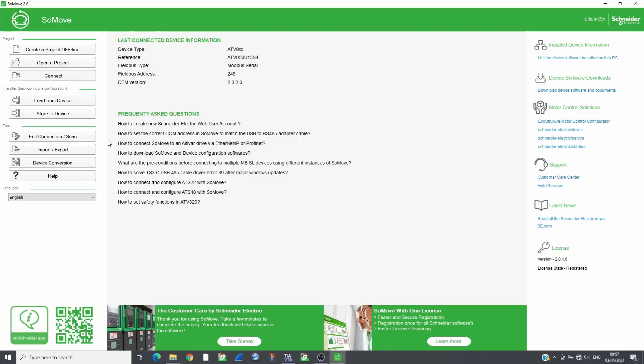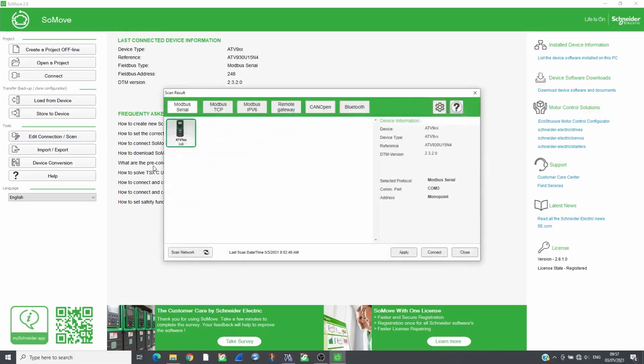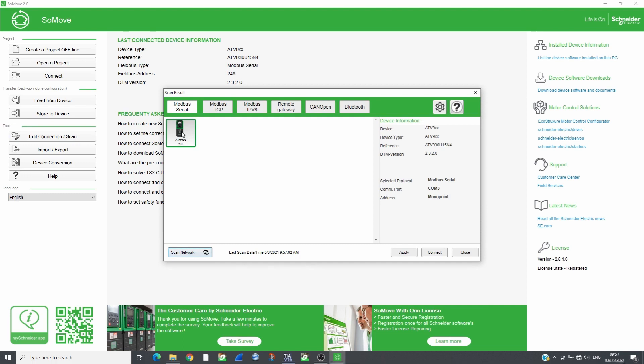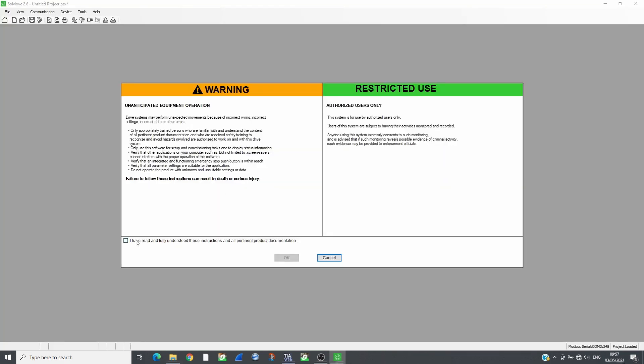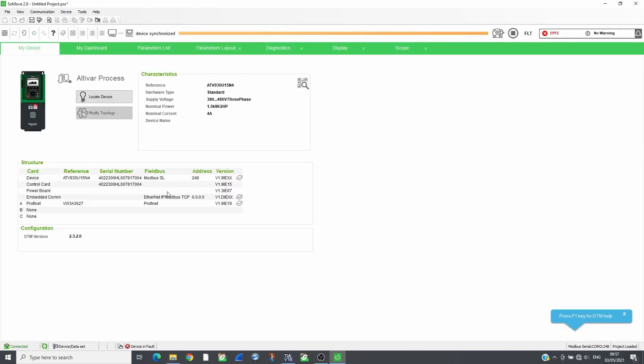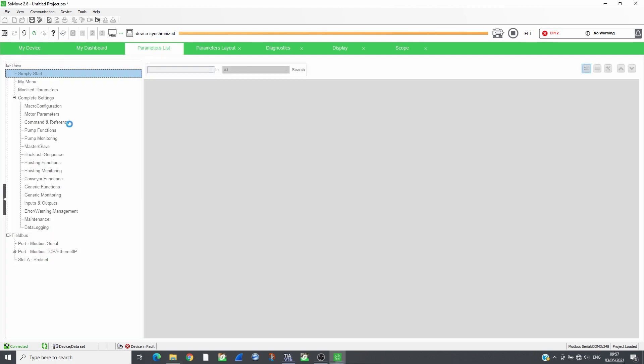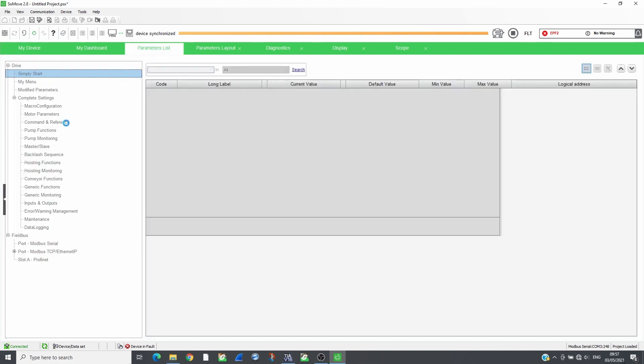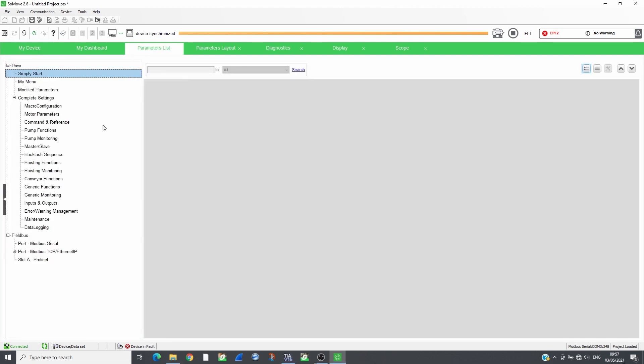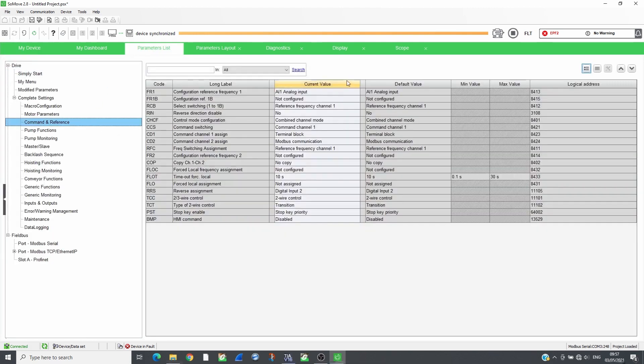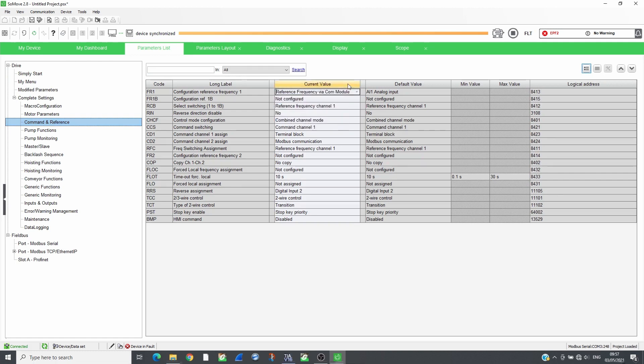Open SoMove and connect to the drive which has VW3A3627 plugged in. Set the reference and command channels to the communication module. The drive will be controlled following CIA402 profile.